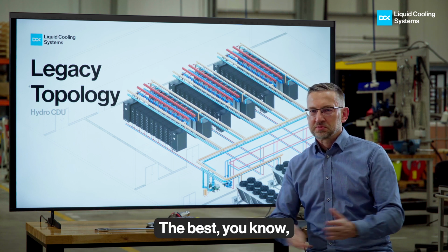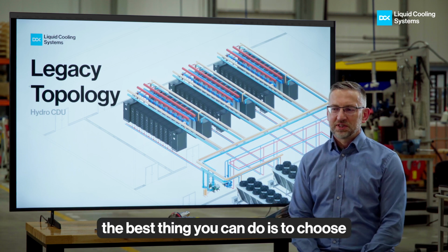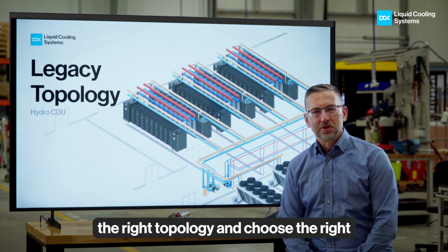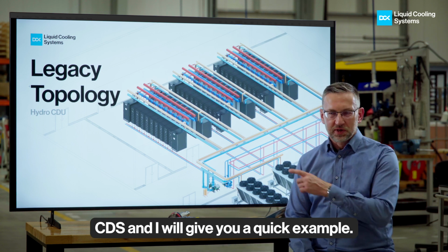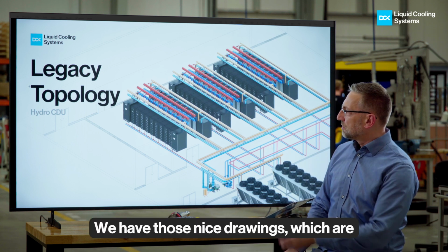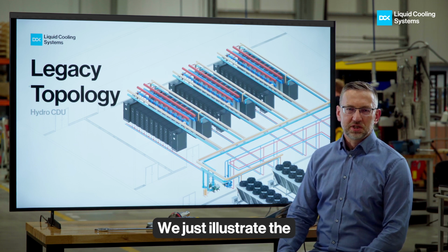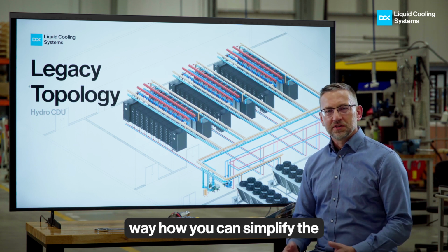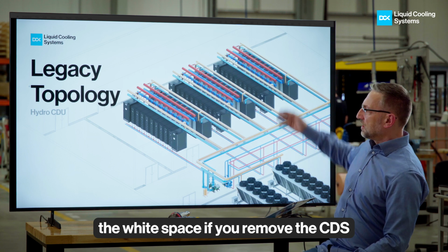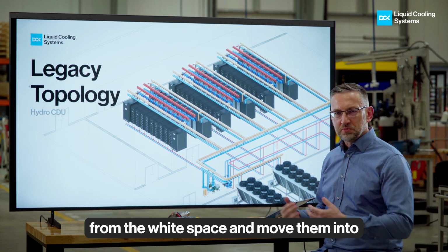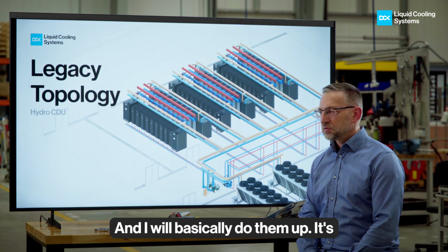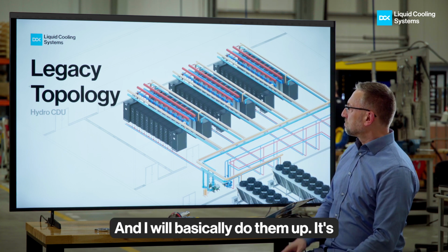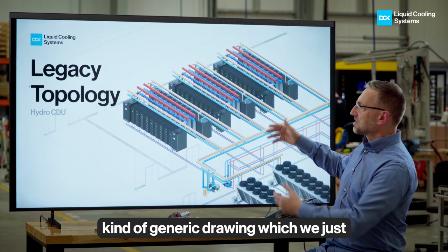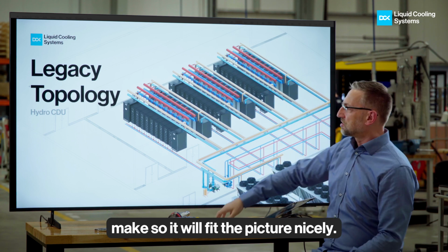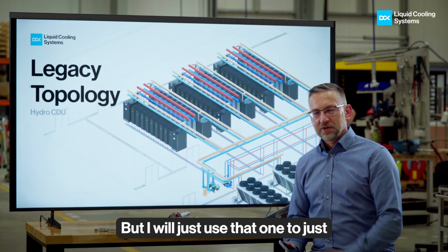Right. The best thing you can do is to choose the right topology and choose the right CDUs. And I will give you a quick example. We have those nice drawings, which are kind of nice marketing drawings, which just illustrate how you can simplify the white space if you remove the CDUs from the white space and move them into the gray space, right? And I will basically do the math. It's a generic drawing, which we just make so it will fit the picture nicely, but I'll use that one to expand on this and explain how we can save.